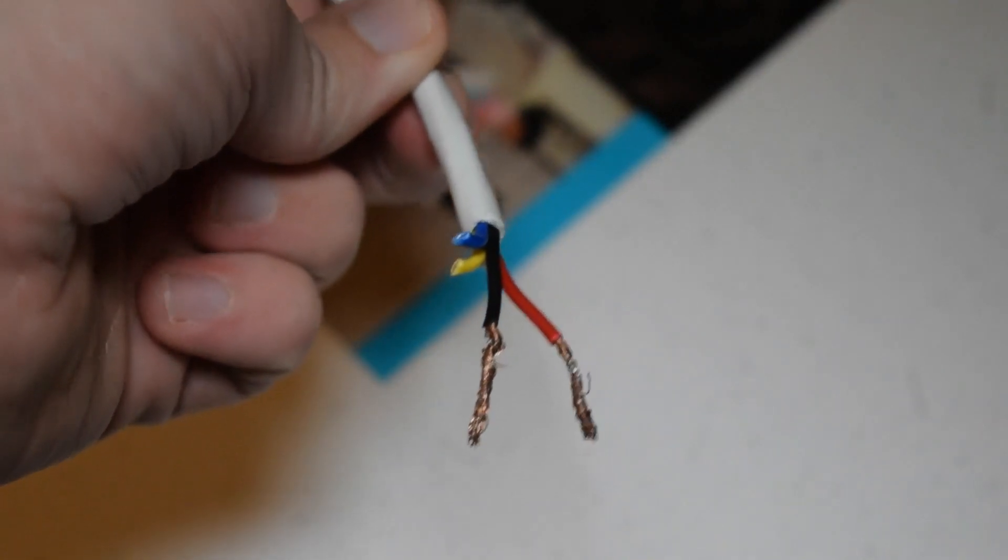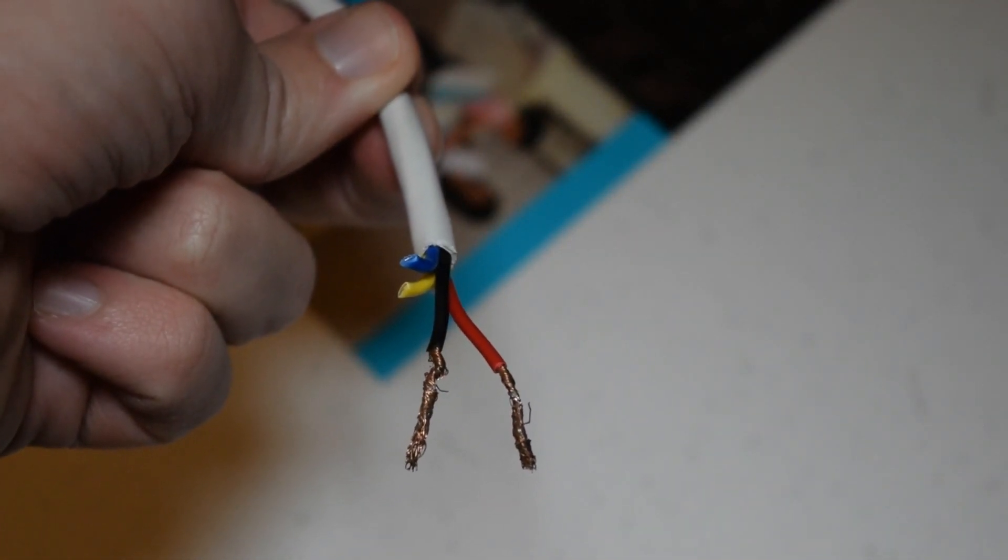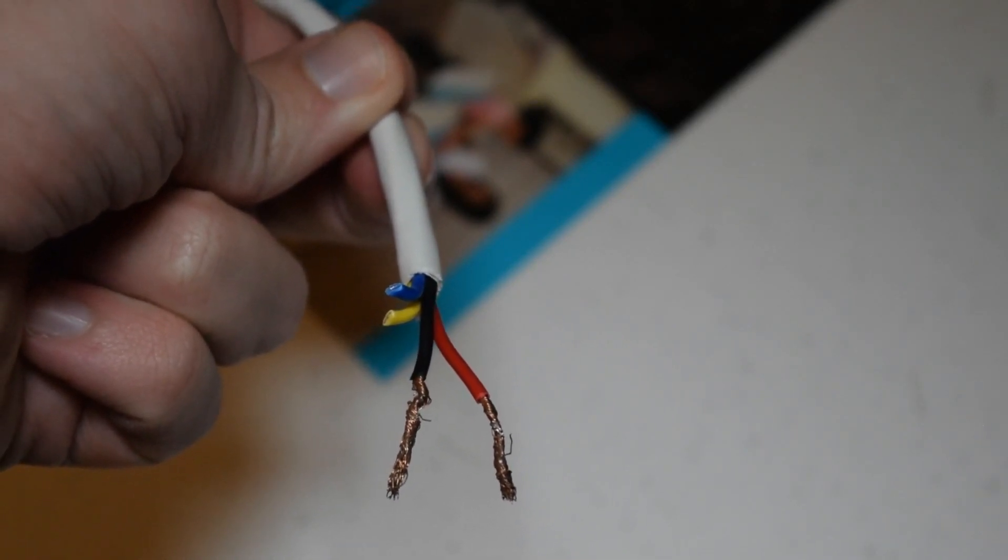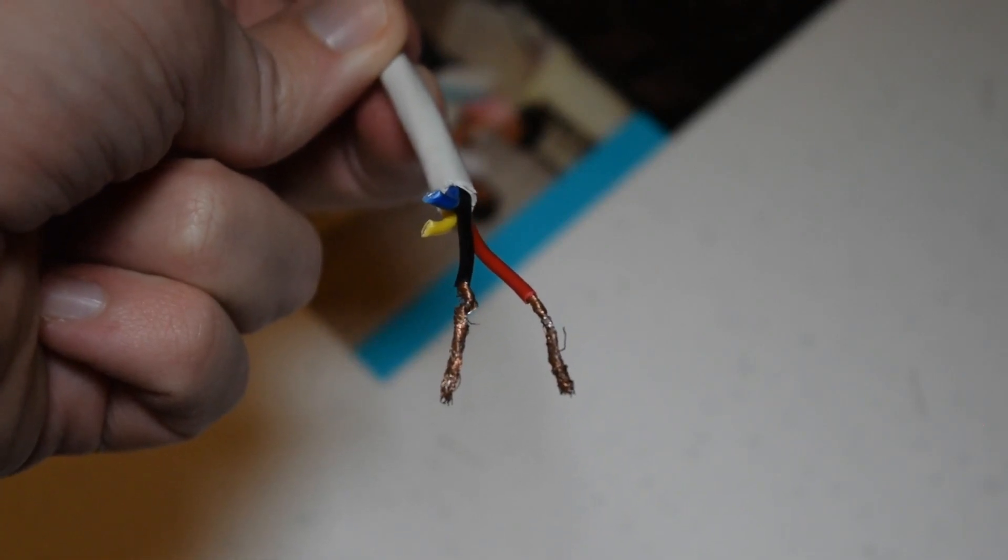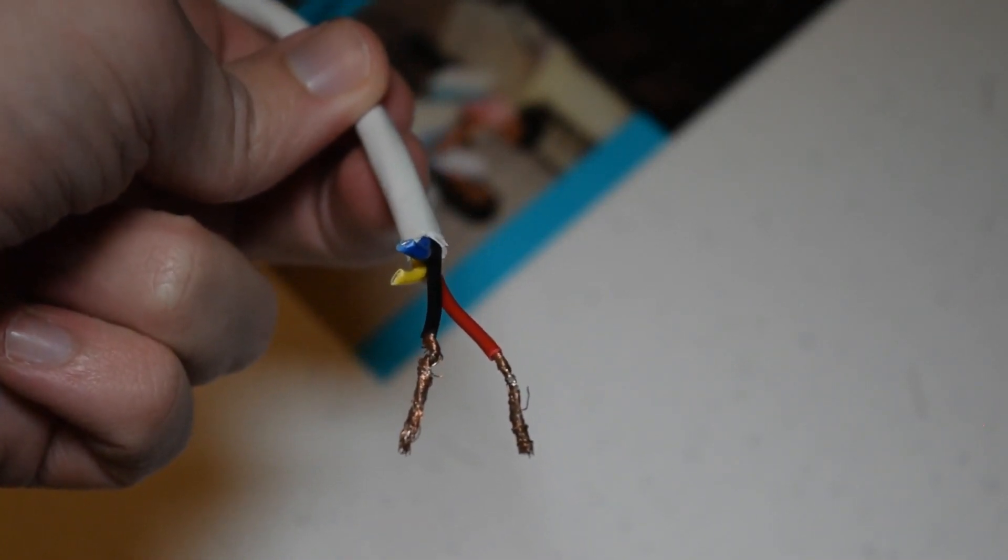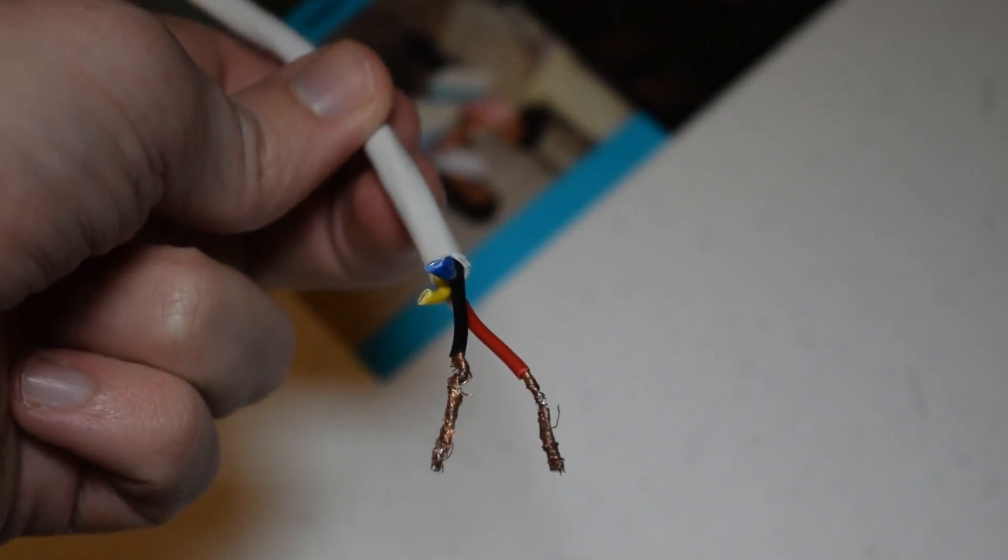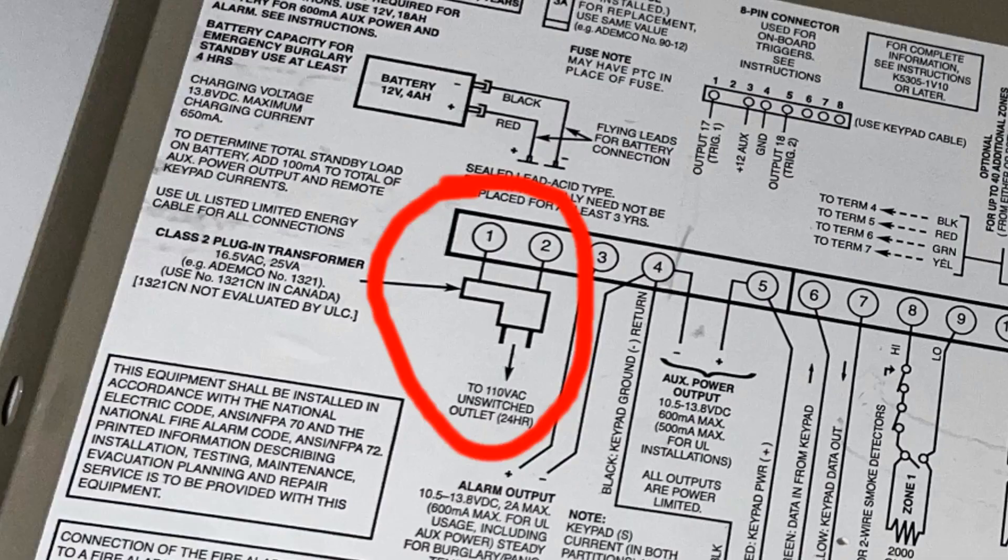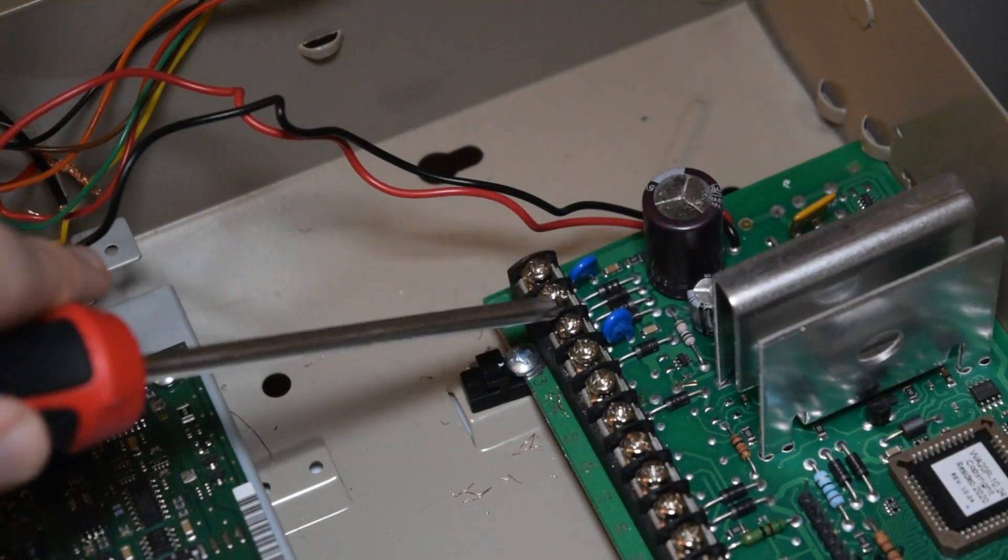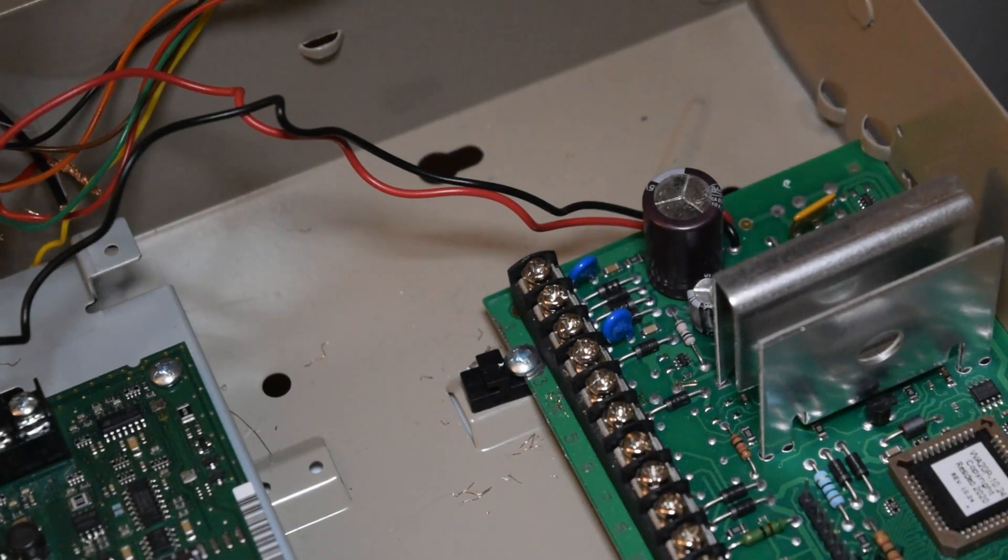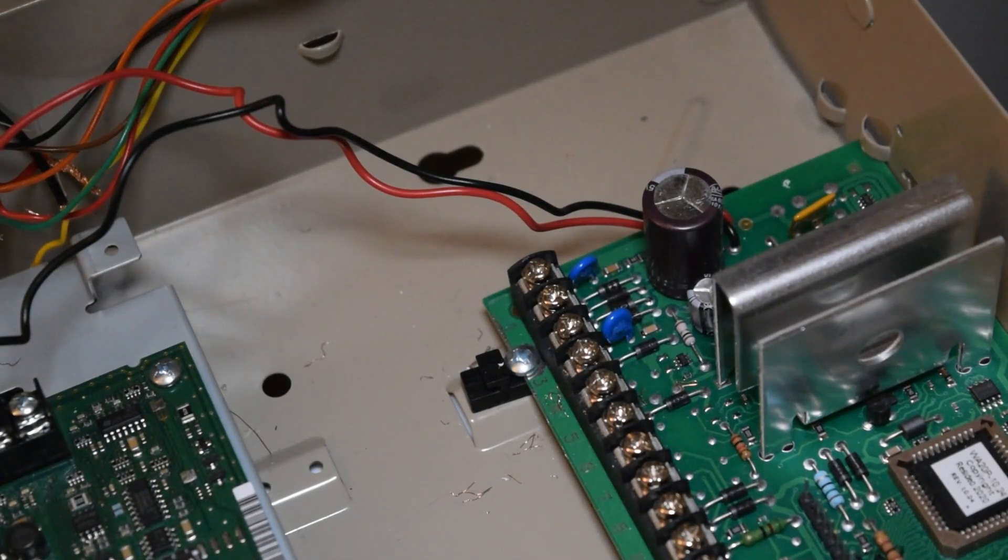So now you're going to take the other end of that wire after you cut it to the desired length and whatnot and repeat the exact same stripping steps. Then these two are going to go into the panel's circuit board. So referencing the schematic, which is on the inside of the panel enclosure's door, terminals 1 and 2, which is right here, 1 and 2, are for incoming AC voltage. And once again, since it is AC, the polarity does not matter. It does not matter what order you put the wires in the terminals.